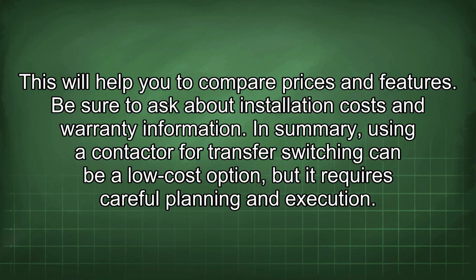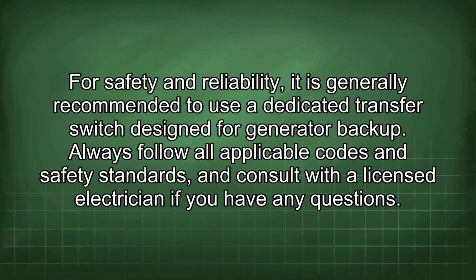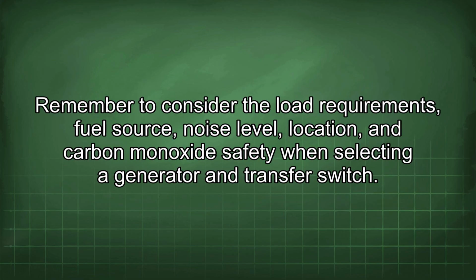In summary, using a contactor for transfer switching can be a low-cost option, but it requires careful planning and execution. For safety and reliability, it is generally recommended to use a dedicated transfer switch designed for generator backup. Always follow all applicable codes and safety standards, and consult with a licensed electrician if you have any questions. Remember to consider the load requirements, fuel source, noise level, location, and carbon monoxide safety when selecting a generator and transfer switch.